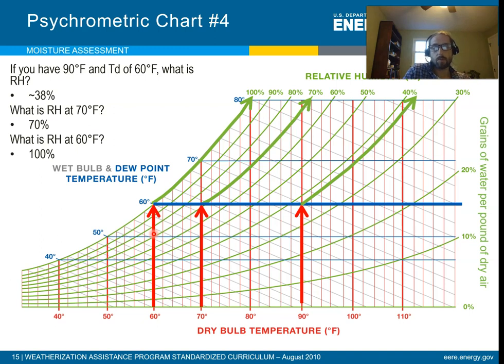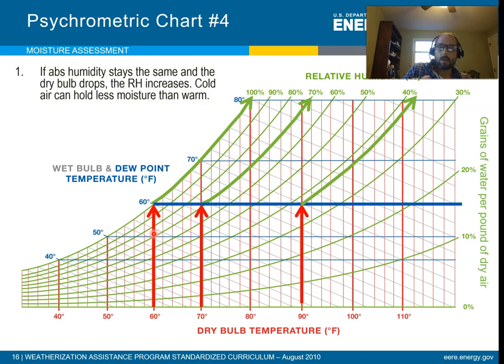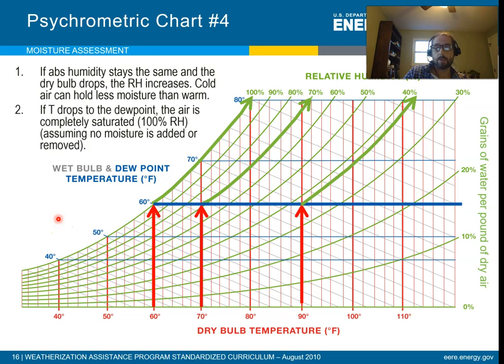And that's what defines the dew point — dew point is the temperature at which you reach 100% relative humidity, full saturation, when condensation starts to occur. If the absolute humidity stays the same and the dry bulb drops, the relative humidity increases, because cold air can hold less moisture than warm air. You warm the air up, relative humidity drops; cool it down, relative humidity increases. Drop the temperature all the way down to the dew point and you get 100% relative humidity — full saturation. This is assuming no moisture is added or removed.